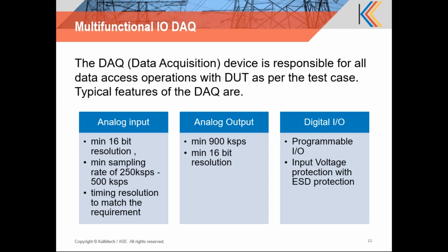It should have a minimum sampling rate to make sure that it captures the signals and data from the device under test. The timing resolution should match the requirement, and there are cases which require an analog output. To create a test environment, we should provide some analog output also, and it can be measured or input into that system or device under test, where we can measure the response from the system. One of the solutions which we have used had 900 kilo samples per second with 16-bit resolution.